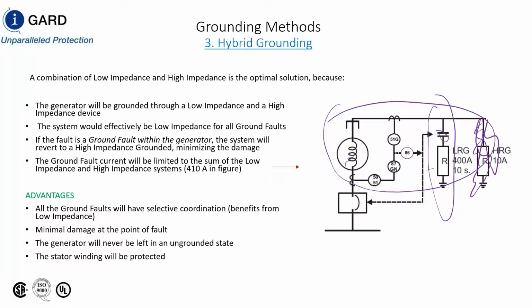and this could be just as dangerous, in fact more dangerous than having the 400 amp resistor there, because think about it, when you have an intermittent arcing fault, and you're going to have an intermittent arcing fault specifically in the stator winding when you have a ground fault in the stator. So your generator is now ungrounded, and you can have catastrophic damages in an ungrounded system during an intermittent arcing fault, and you're going to have over voltages on the system of 6 to 8 times the normal system voltage. And there's been documentation of how that has been more catastrophic than leaving the 400 amp resistor there.